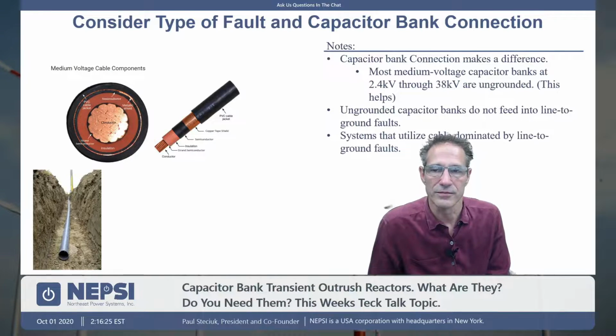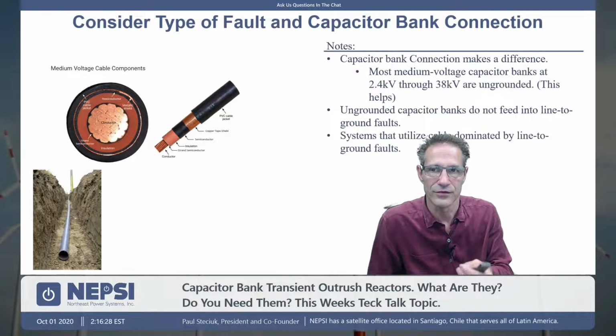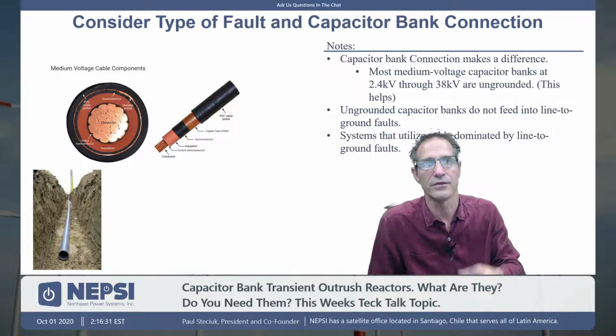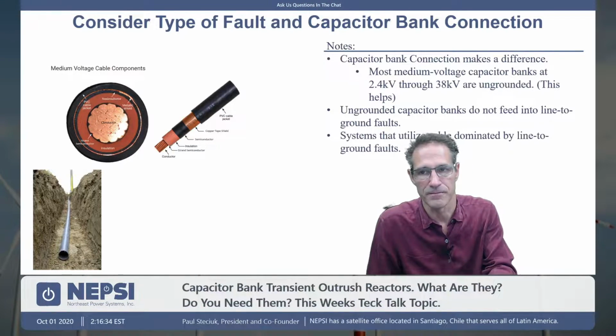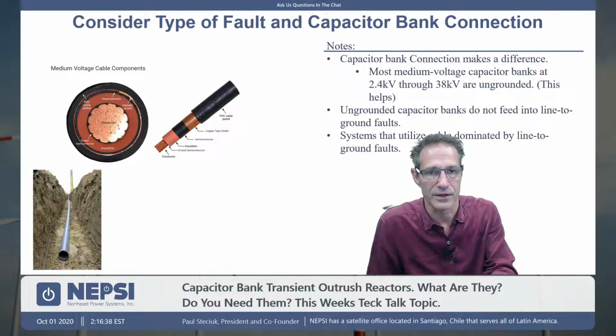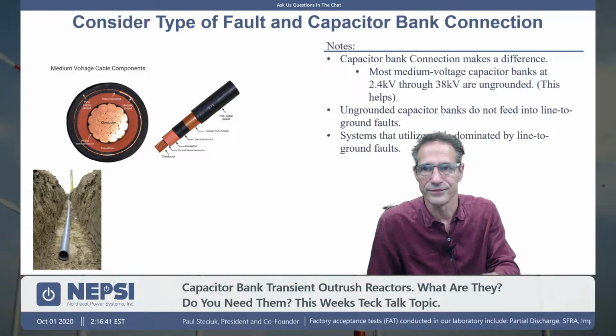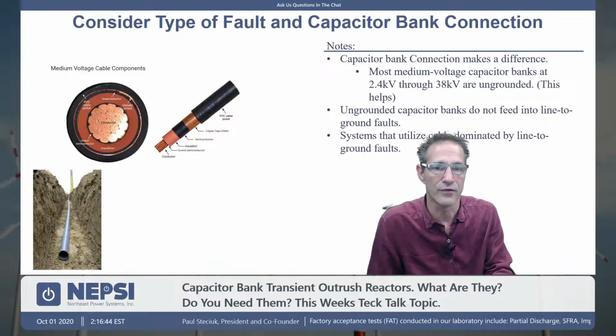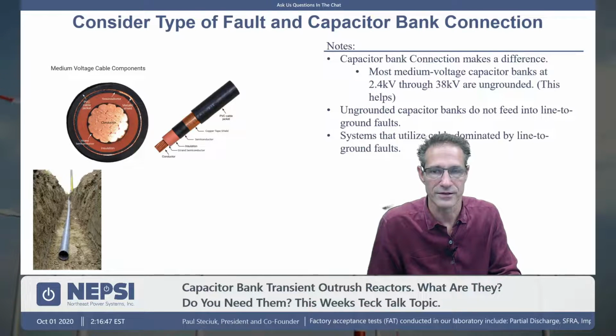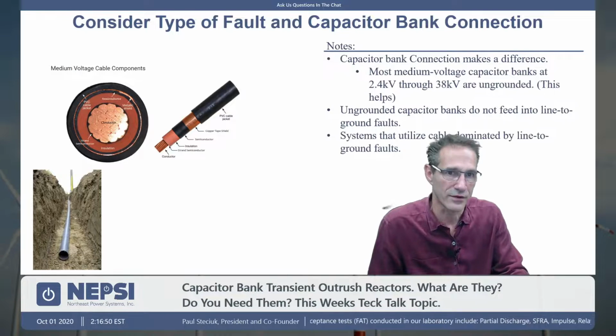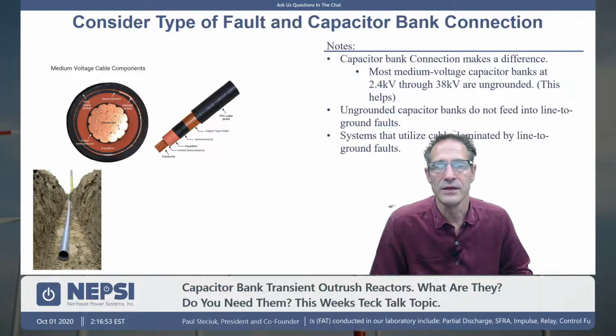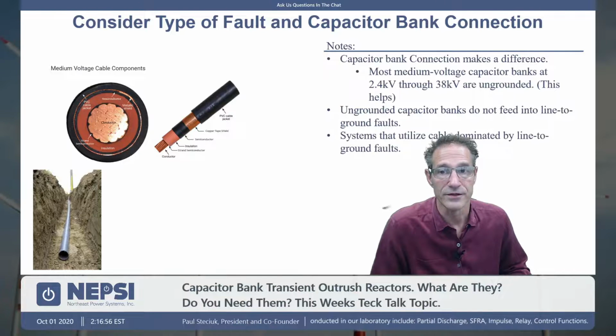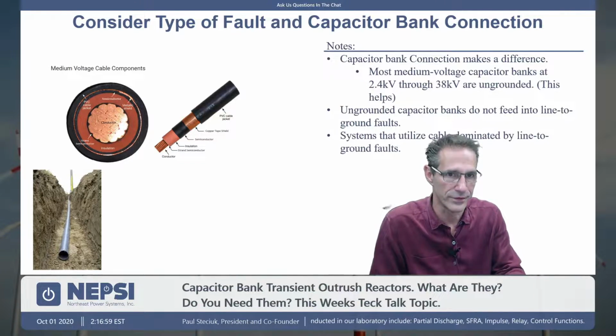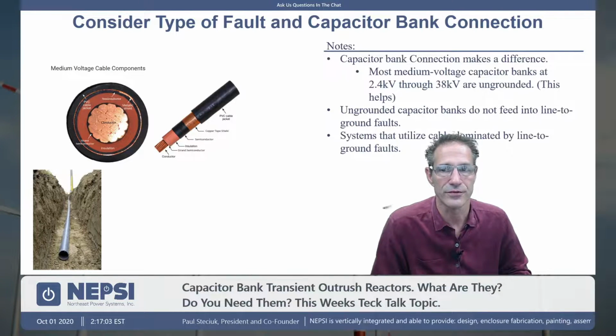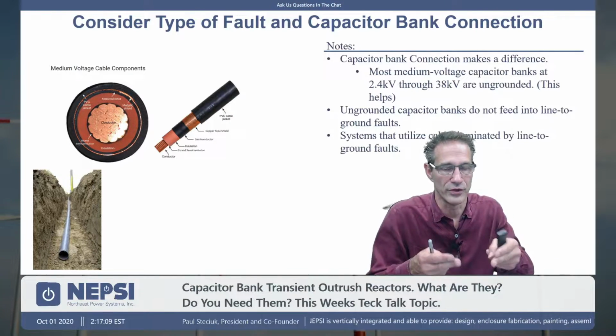So this is something to always think about when you're thinking about adding outrush reactors to your cap bank. Think about the type of fault you have, and also think about the connection of your cap bank. So I would say, by and large, nearly all banks are left ungrounded, which means that for all line to ground fault conditions that exist outside the substations, the capacitor banks will not contribute fault current. If you're thinking about a phase-to-phase fault, the condition there would be like radical 3/2. It would be the typical value. It's not 100% of the three-phase value. It's a percent of it. So that outrush current will be, again, less of what that breaker has to withstand.